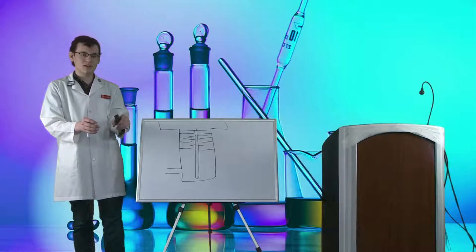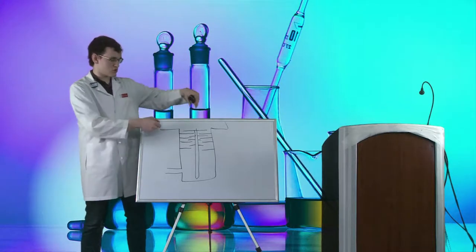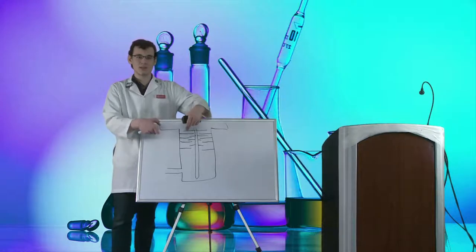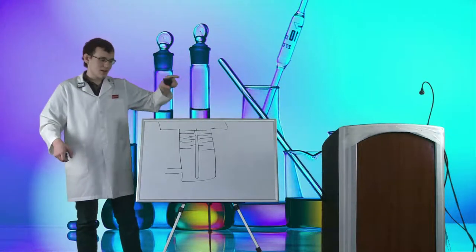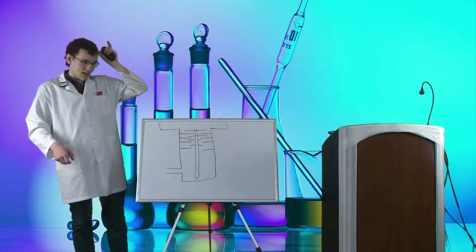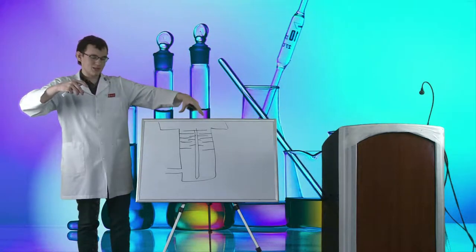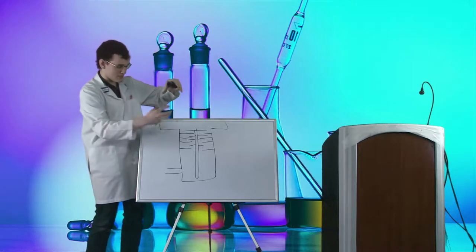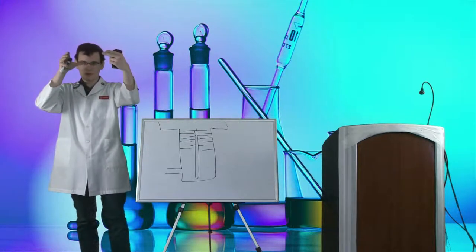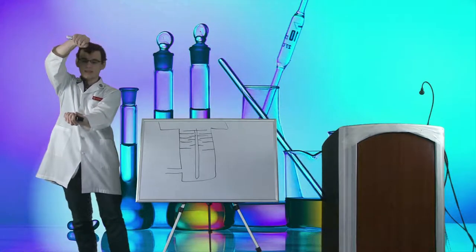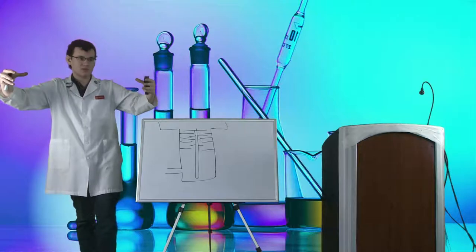When they crash, that much steel moving is enough force to actually shear the bolts mounting the pump, and the pump can go flying off to the side and put a hole in whatever vacuum machine you're running. I've seen a microscope like ours where the turbo molecular pump crashed — it was spinning so fast it tore itself off its mounts, twisted 90 degrees, and pushed out the steel panels on the side of the microscope. That's how much energy it takes to pump this level of vacuum.